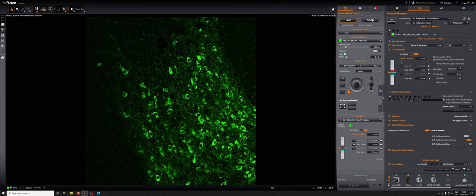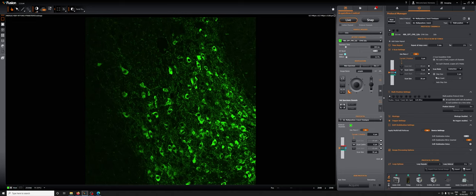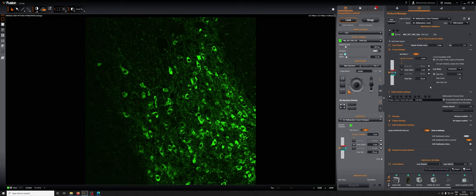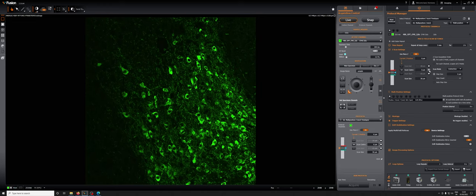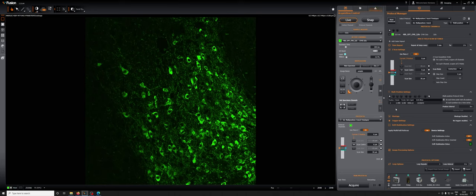Now that we have determined what the scan size should be, here come the critical steps. If we've selected center size, we need to make sure that before we add the point, we do the following: we go to the center, so we want to make sure the piezo is in the center, we click drift stabilization active, and then we add the point by clicking here.